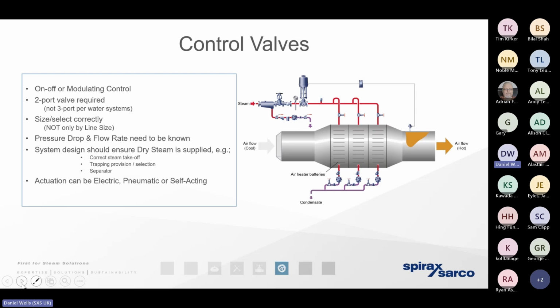So if we're moving steam in the pipework at a very high velocity, 40 meters per second, 90 miles an hour, as the steam moves across the control valve, if that control valve's modulating closed and operating very, very close to its seats, the speed of the steam can increase tenfold. So the steam can be moving across the control valve at maybe 350, 400 meters a second. That's not far off the speed of sound. You can appreciate that any moisture, any rust, any scale is going to create significant problems to the control valve, resulting in a lot of damage, a high cost of ownership. But ultimately, it's going to affect the process because we're going to have steam moving onto the heat exchanger when it's not required.